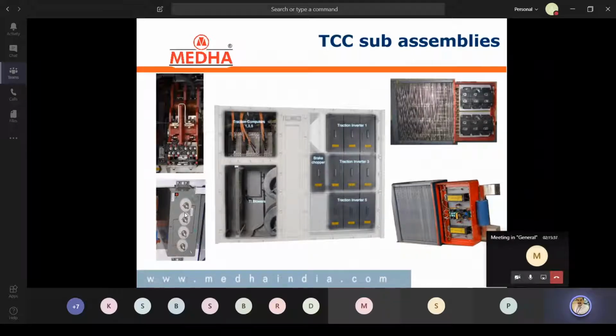By default, controlling is based on the PT100 probe sensor. If that is declared faulty, it automatically switches over to the thermal switch. So each IGBT is provided with one PT100 probe and one thermal switch. Like that, in each module there are two IGBTs, top IGBT and bottom IGBT: U top, U bottom, V top, V bottom, W top, W bottom, like 6 IGBTs. Total 3 phase modules form one inverter.